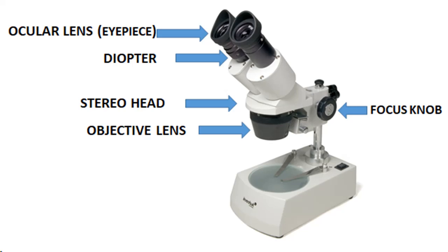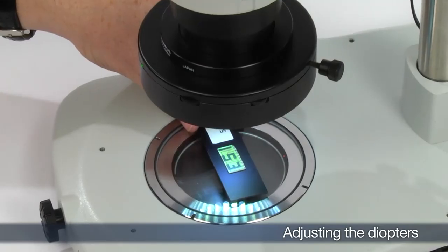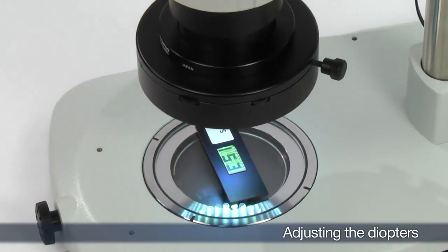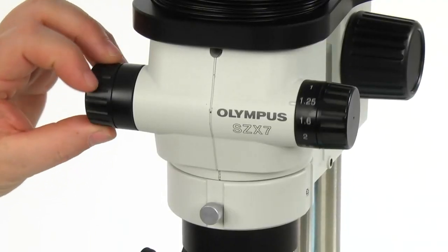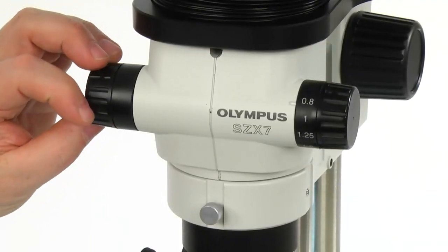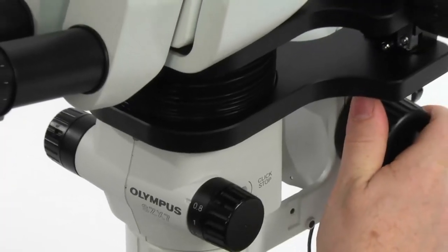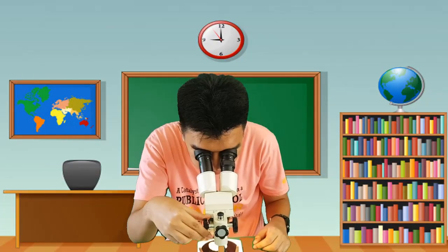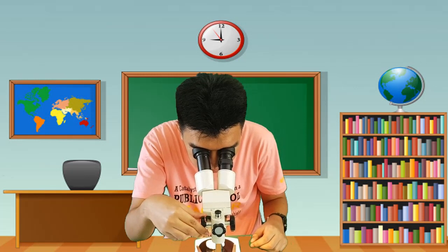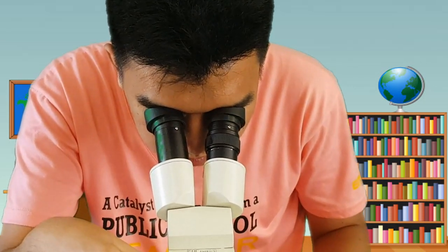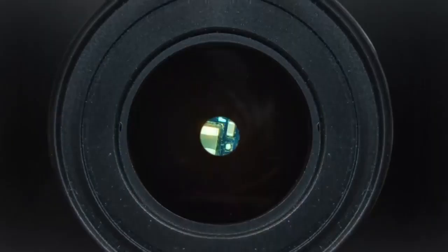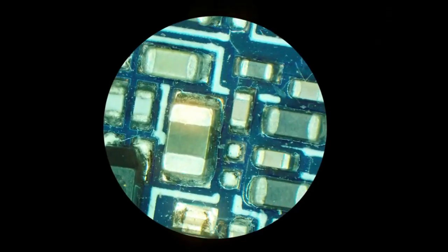Focus knob. Stereomicroscopes usually have one focus knob. It helps move the head of the microscope up and down to bring a sharp image of the object. Most dissecting microscopes have standard rack and pinion focusing. The rack is the track with teeth, and the pinion is the gear that rides on the teeth. The knob helps the pinion move along the rack.